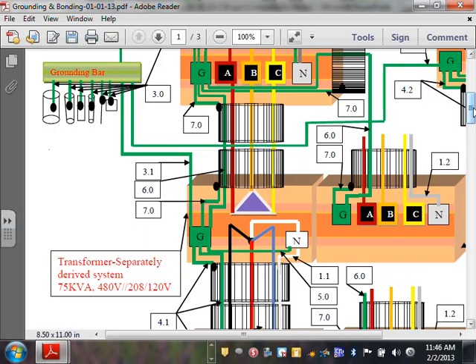Does that make sense? If you had supplemental grounding bars in a closet, if that was tied back to the main grounding bus, you could tie that transformer into that grounding bar. If we have supplemental grounding bars, yes. As a matter of fact, they do this all the time. What they do for risers is they take a ground, but you have a requirement of 3/0. It has to be 3/0. You take a 3/0 from this ground bar, and you go through the riser, through the building, to the floor to the closets, and you tap into and feed these transformers. Very commonly used. But you're still going to one point, though. That's why in bigger systems, guys, moving that bar away is the best idea because you have a lot of things to bond to, and you don't want to put things inside the switch gear.